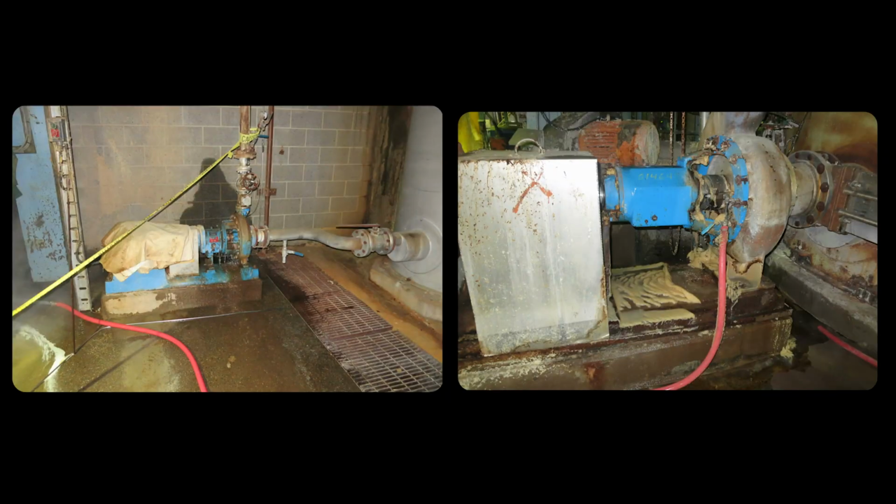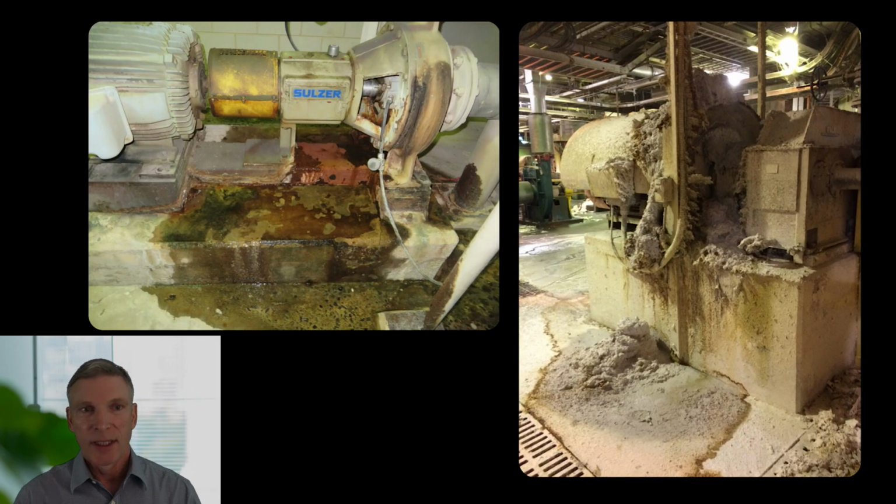This is kind of what I see when I'm out in different plants. You see leaks, water leaks. The water gets into the oil, you ruin the bearings; the water gets into the motor, the electrical connections, you get shorts, you get corrosion. The pulp is leaking from a pump here, causing corrosion on the base and all the equipment around it. Plus, if things are leaking, it's very difficult to see if there's some other problem going on or to identify a small leak that's starting somewhere if you've got process liquids everywhere.